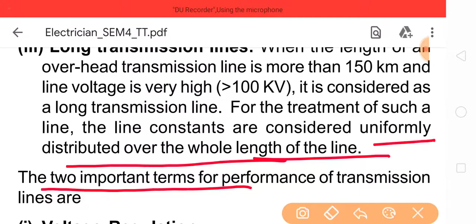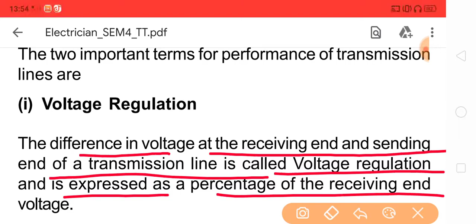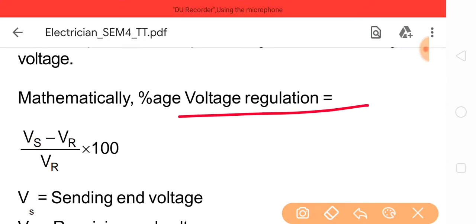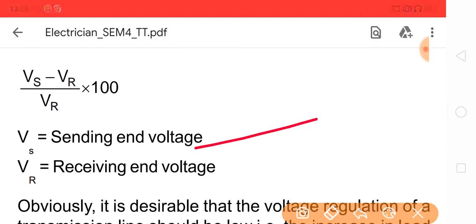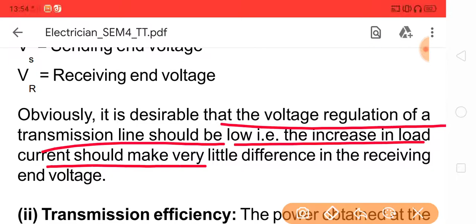Voltage regulation. The difference in voltage at the receiving end and sending end of a transmission line is called voltage regulation and is expressed as a percentage of the receiving end voltage. Mathematically, percentage voltage regulation is equal to (Vs minus Vr) divided by Vr into 100, where Vs is the sending end voltage and Vr is the receiving end voltage. Obviously, it is desirable that the voltage regulation of a transmission line should be low. The increase in load current should make very little difference in the receiving end voltage.